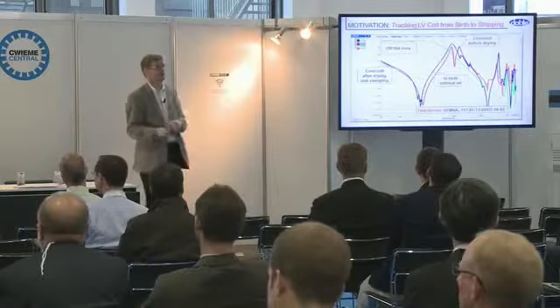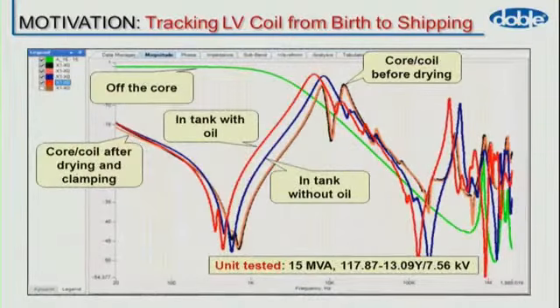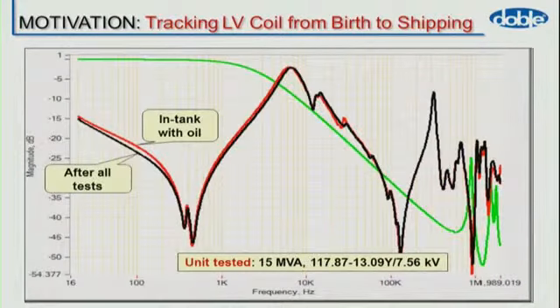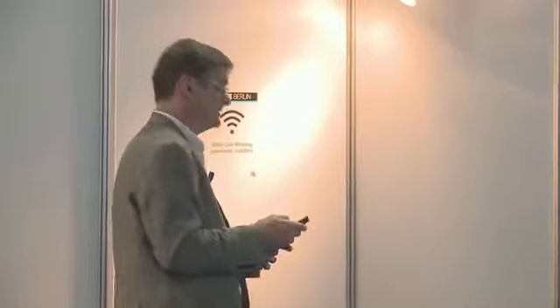You add oil, you get a different result. You dry and clamp, you get a different result. You add oil. There's lots and lots of variation. What is best to have is a reference. So these are actual valid results that you can use in the factory. There used to be a guy, Jim Fivey, up at Transformer Manufacturer in Edinburgh, and he would use SFRA in the factory as the coils were moved around to check to see if there's any movement or damage. And it works. But you need someone who knows what they're doing.